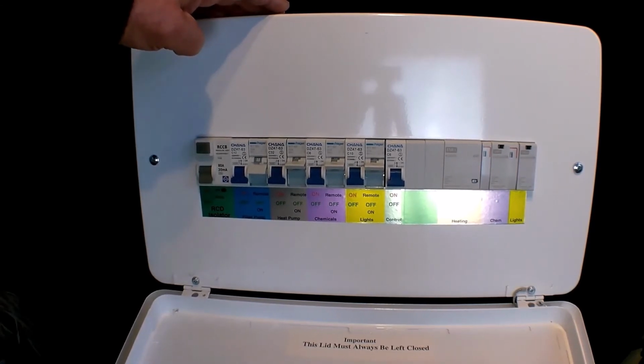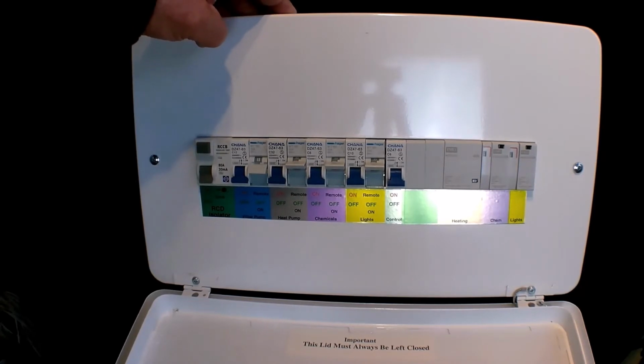I would always reckon that while you're doing the groundwork and you're putting the cables in, put a cable down there, so if the equipment's going to need a hardwire, you've got it there. And it can always be used, if not, for low voltage signalling, so you can switch things from the house end if you want to, without any crossover of where the mains are coming from and earthing problems.